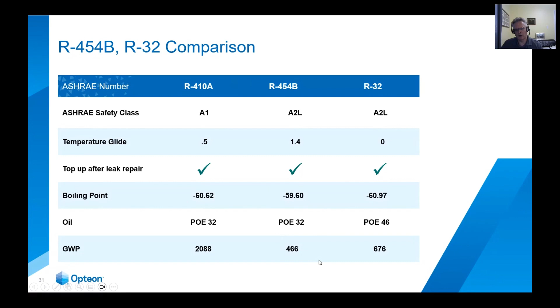And just to highlight one thing to keep in mind, from what we've heard from the manufacturers, although they are all POE oils, there may be different viscosities of the oil, so it's something to watch for. The other thing, certainly, is the GWPs of these refrigerants are much lower than the 2088 of 410A, and both are below the 700 limit that's in place in the US, well below that 700 limit in both cases.